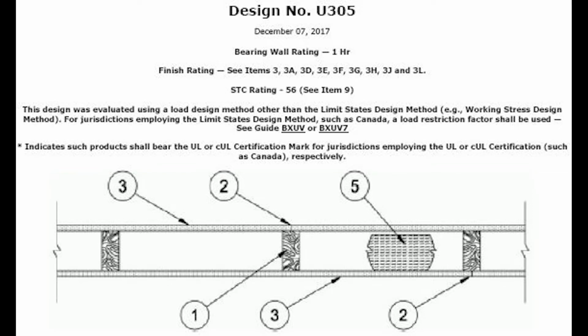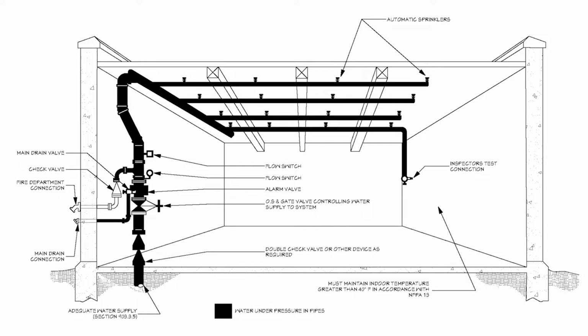The building itself should be already capable of slowing the spread of a fire, as exterior walls and walls that divide the building into different spaces should be fire-rated walls. Typically, a 1-hour rating is the lowest allowed for demising in exterior walls. This is not the only way to prevent the spread of a fire, however, as it is common to find fire sprinkler systems in commercial spaces. Though fire sprinklers aren't always required in a given commercial space, it has become the standard for most commercial buildings to have a working, custom-designed fire sprinkler system.